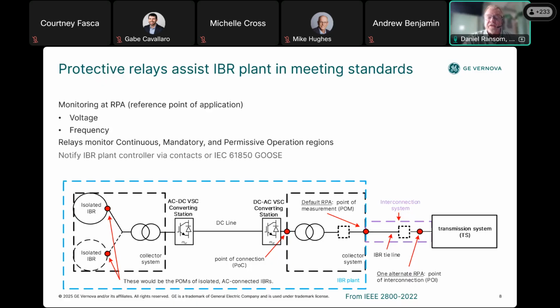The relays can notify the IBR plant inverter controls of operation in the continuous, mandatory, and permissive operation regions via contact closures, sending it back from the relay at the point of measurement to the IBR controller, and thus the IBR controller gets immediate feedback. Relays send operational data back to the controller, and thus they can curtail the output of the IBR or allow it to trip, or cause it to trip, at the point of interconnect.